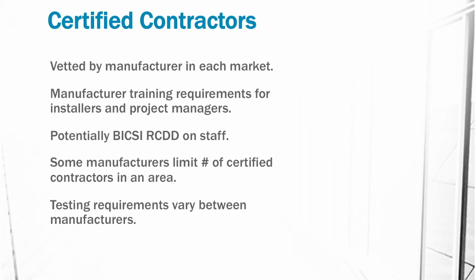Another potential requirement, the manufacturer may require that the contractor have a BICSI RCDD on staff. This is listed in my Division 27 requirement. If I've got, remember, that Division 28 specialty telecom for electronic security section, and I just have copper, then I'm going to delete that requirement from my spec. But if I have fiber, I want to do a little more due diligence and expect a higher level contractor, so I'll make sure I have that in there as a contractor requirement.